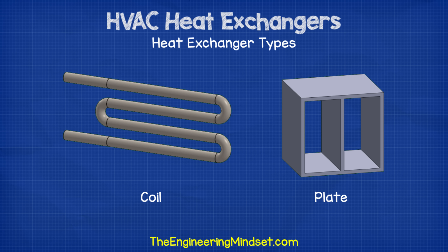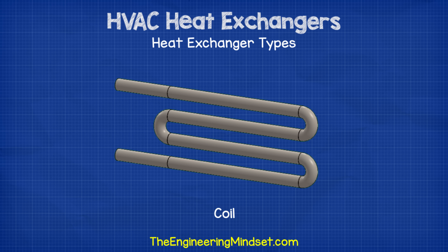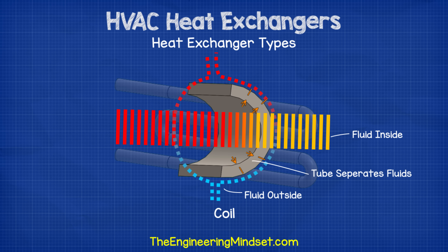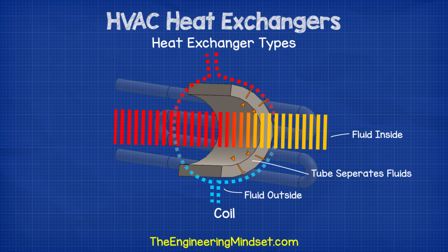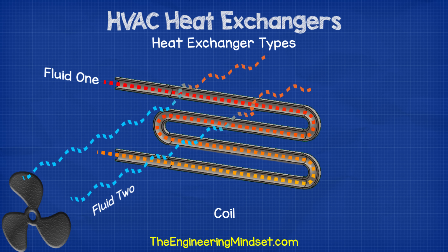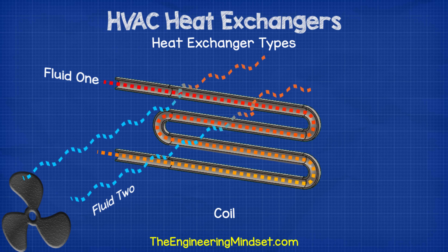Most heat exchangers follow one of two designs: either coil or plate design. Coil heat exchangers in their simplest form use one or more tubes which run back and forth a number of times. The tube separates the two fluids — one fluid flows on the inside of the tube and another flows on the outside. Heat is transferred from the hot inner fluid to the tube wall via convection, then conducts through the pipe wall, and the outer fluid which is cooler carries it away through convection.